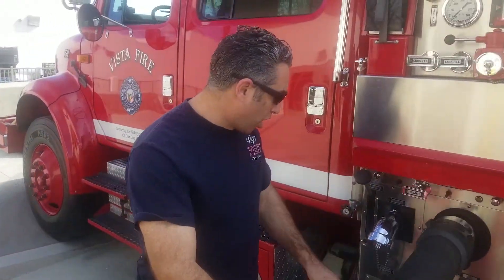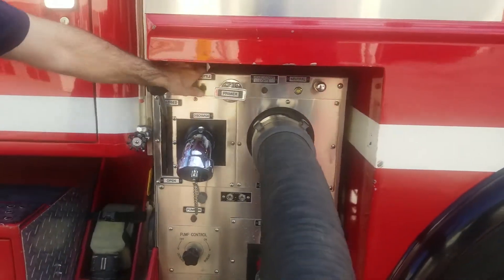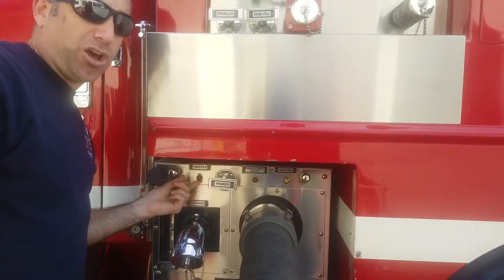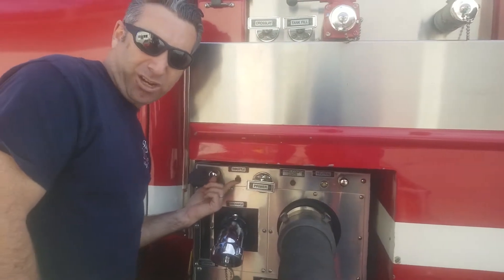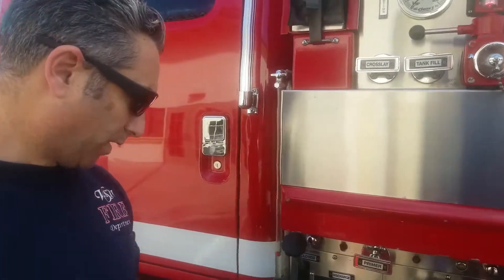We're gonna make sure that all of my valves are closed. I'm gonna turn the pump on and put my panel lights on. We're gonna engage the throttle by holding the toggle switch up until the throttle and high idle engages. Then we're gonna go ahead and throttle up the pump just until it engages the pump.